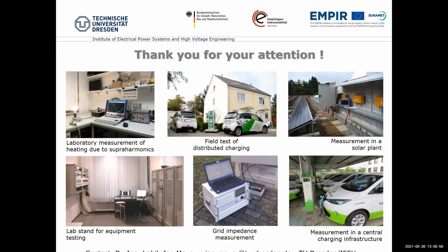You've mentioned propagation, and I want to check if you have noticed or studied propagation up to the MV level. Well, we started to look at that. A few years ago we measured the transfer characteristic of a typical MV-LV transformer in our lab, and there we could see similar behavior. There is a pretty efficient damping, but at some frequencies you can even have a little amplification, though it mainly depends on the impedance situations.